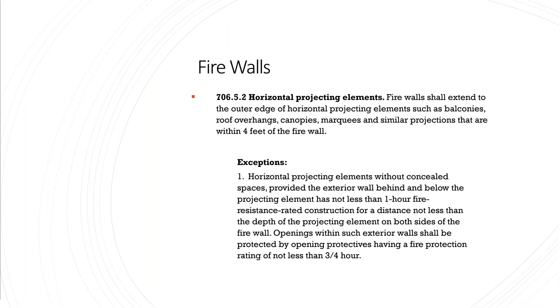Number 1, horizontal projecting elements without concealed spaces, provided the exterior wall behind and below the projecting element has not less than 1 hour fire resistance rated construction for a distance not less than the depth of the projecting element on both sides of the firewall. Openings within such exterior walls shall be protected by opening protectives having a fire protection rating of not less than 3/4 hour. So again, this exception is talking about when you have a projected element that doesn't have a concealed space, then you do the following here.